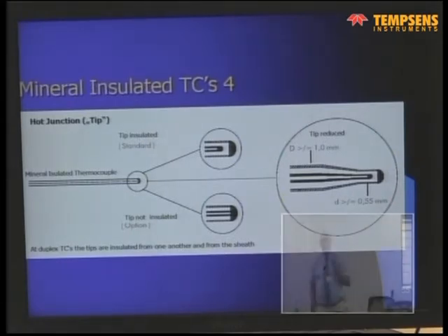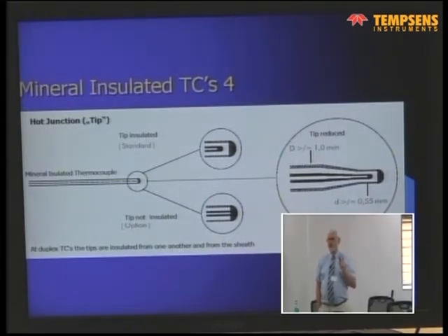So you need a meter with a very good insulated input against mains and ground. Mainly you have what is called a floating ground, but this makes it not ideal for precise measurements. So normally, and most of the vendors say, when you do not make any mention in your order, then it is always an insulated thermocouple.